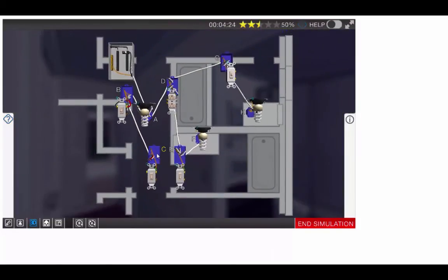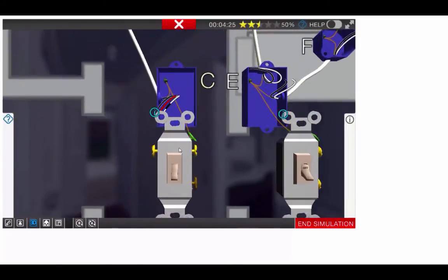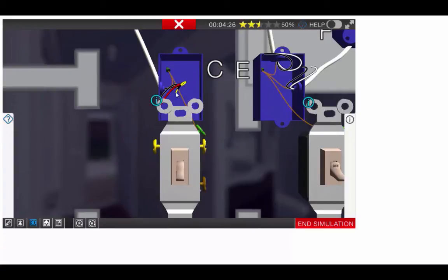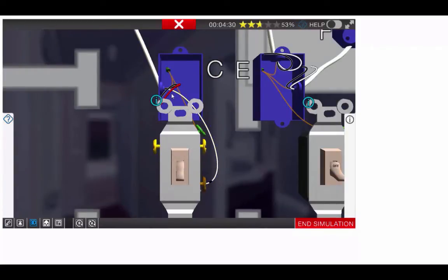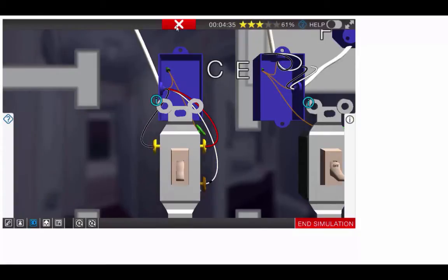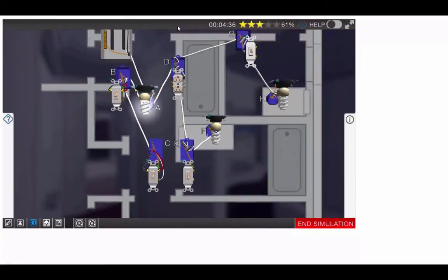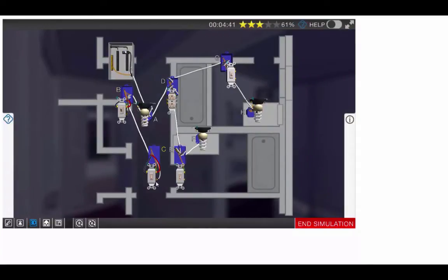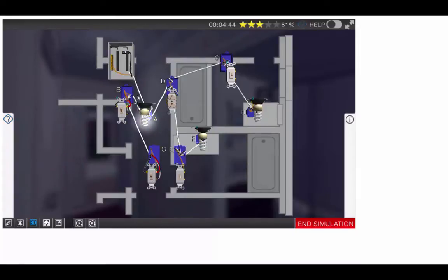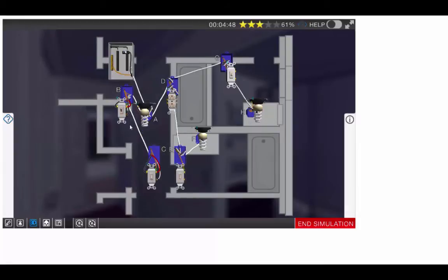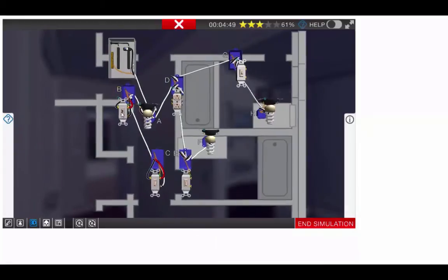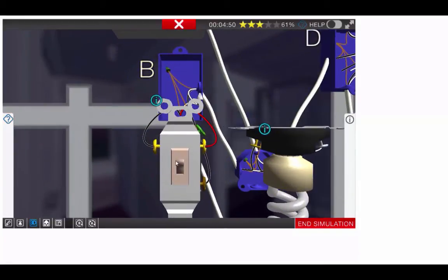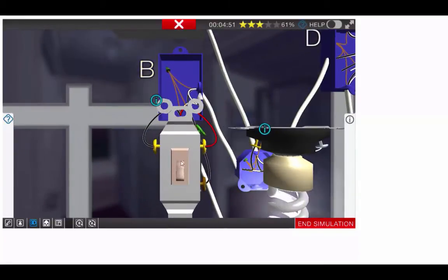Now when we move down to box C, remember, we re-identified our hot with black tape. It goes to our common. Then we'll add our travelers to each terminal. This will complete box B and C. And you notice that since this side of the circuit is directly wired from the panel, the light fixtures are on, and we can turn the switches off and on and check our circuit.